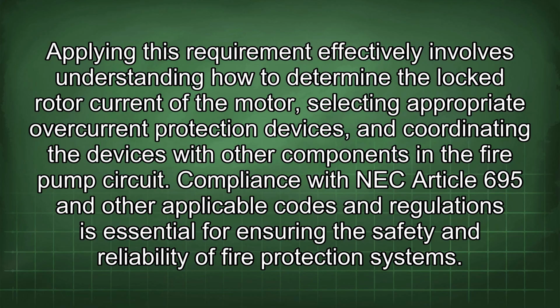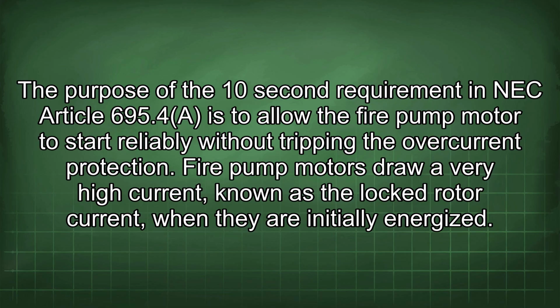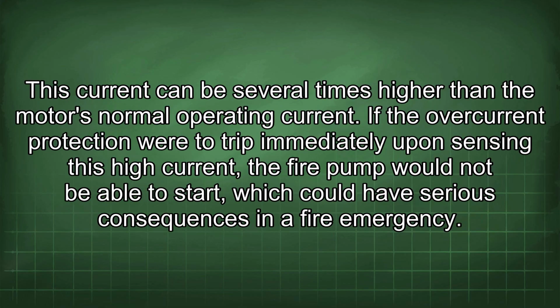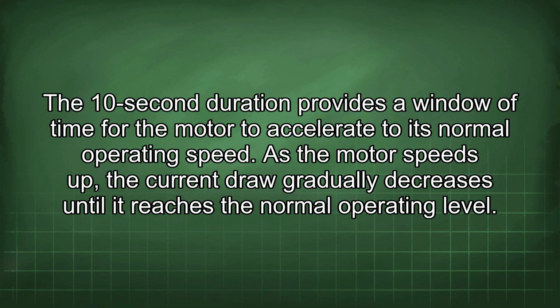The purpose of the 10-second requirement in NEC Article 695.4 is to allow the fire pump motor to start reliably without tripping the overcurrent protection. Fire pump motors draw very high currents, known as the locked rotor current, when they are initially energized. This current can be several times higher than the motor's normal operating current. If the overcurrent protection were to trip immediately upon sensing this high current, the fire pump would not be able to start, which could have serious consequences in a fire emergency. The 10-second duration provides a window of time for the motor to accelerate to its normal operating speed.